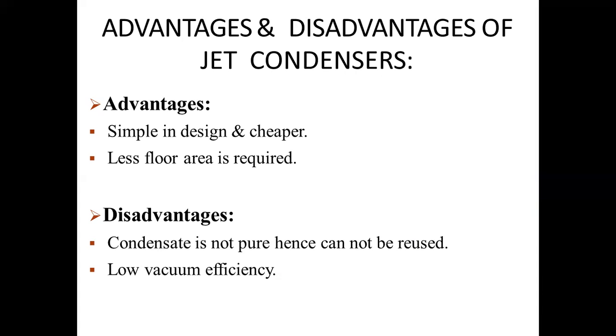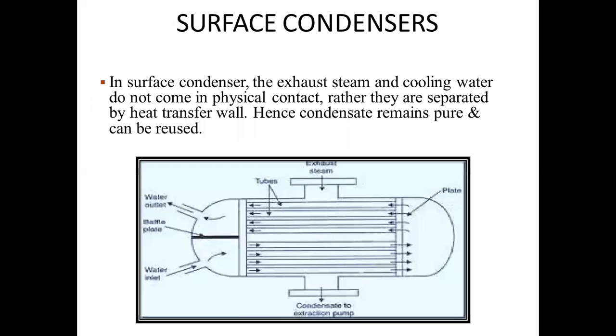Advantage is that it is very simple in design and cheaper, and very little floor area is required, while the disadvantage is that condensate cannot be used for the boiler as this water is not pure. So if we want to use that water, we have to treat this water, and very low vacuum efficiency is there. Next one is surface condenser.